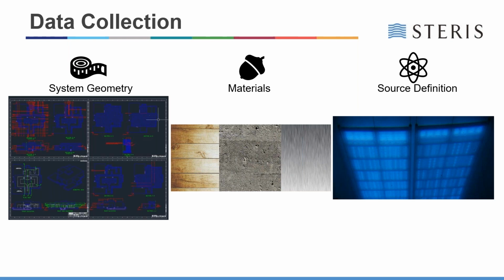So if we were to think about these three materials and the same thickness of each material, we'll say something like 10 centimeters, you could expect that from 100% of a 7 MeV X-ray spectra impinging on 10 centimeters of these materials, roughly 80% would get through if you were using wood in this simulation, and 40% would get through if you were using concrete.